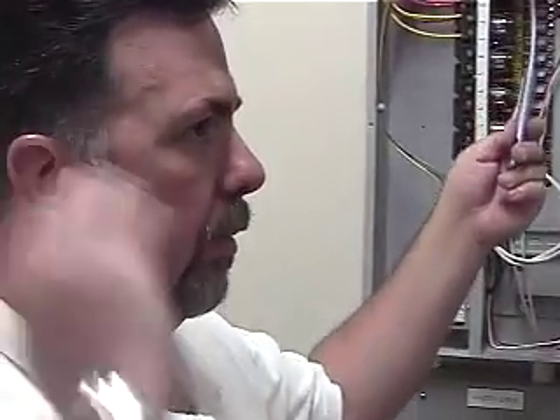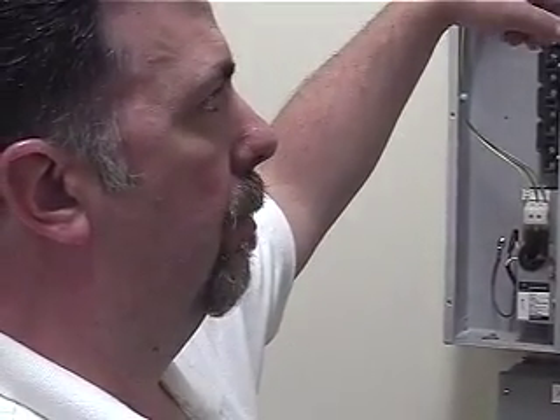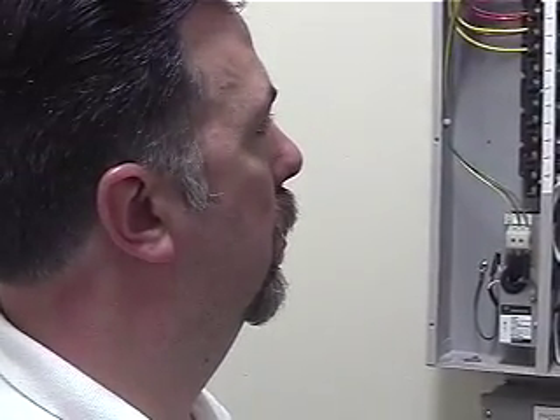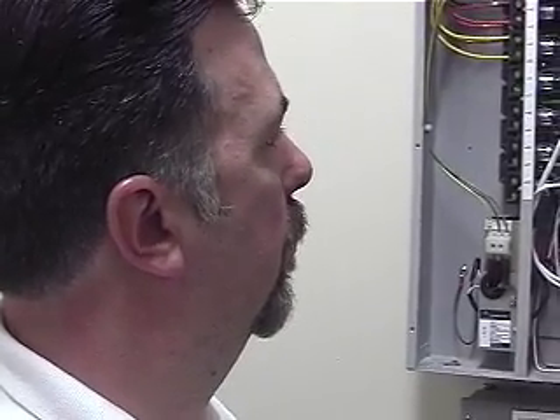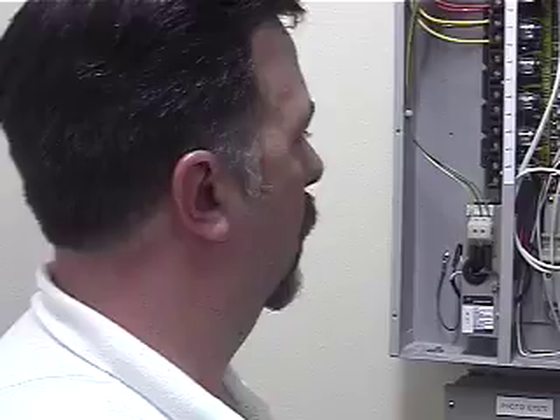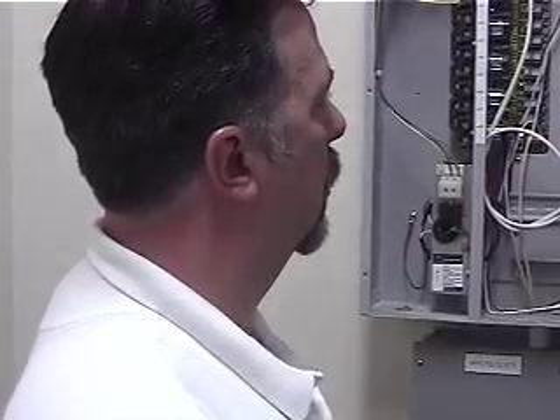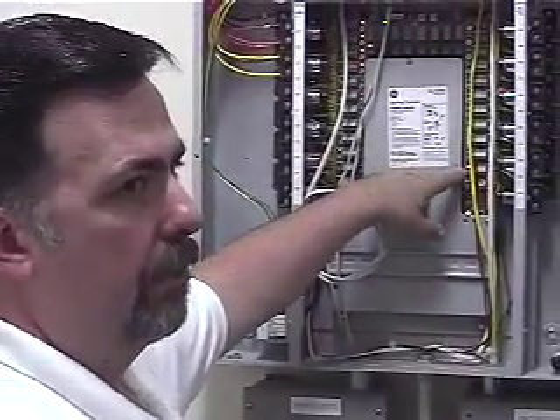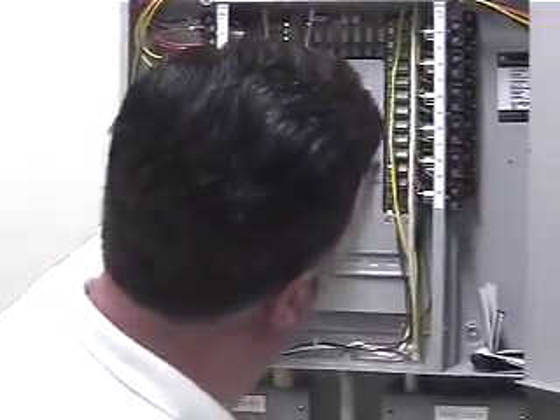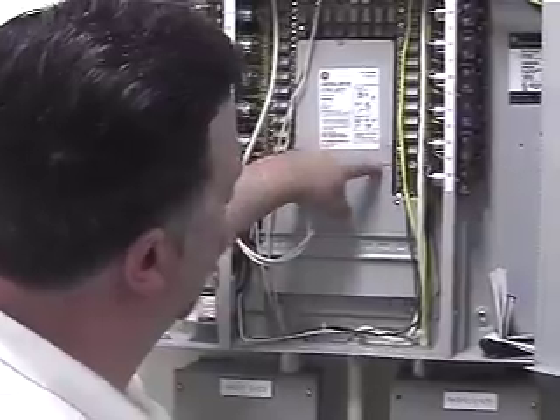Did you say there were 3 photocells? Yeah, the other one's in one of the electrical rooms on the other side on level 2. And it's picking up the ambient light. In the big area? Yeah, that area over there. The photocells for these are located, one's on the roof and one's in here. So all that is a contact closure then for this. Yeah, it pulses on and off, so that gives it the start. So you can see that light's on right now. So it's calling for lighting inside, but the roof one is off.